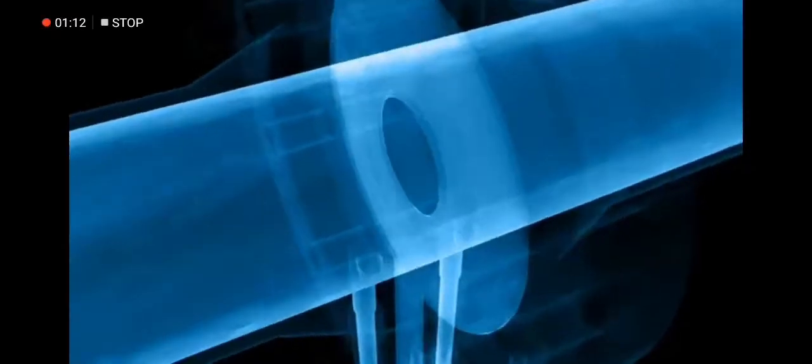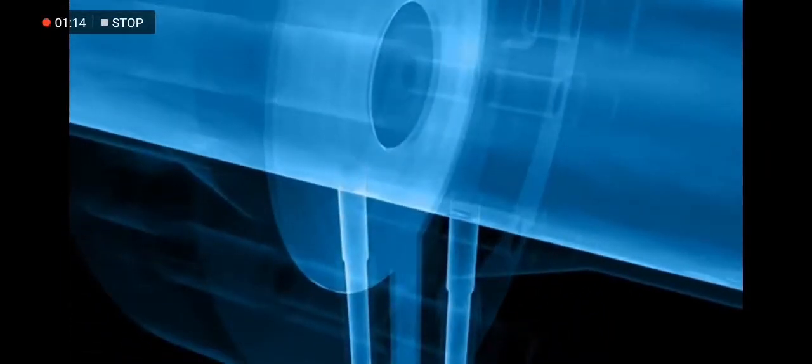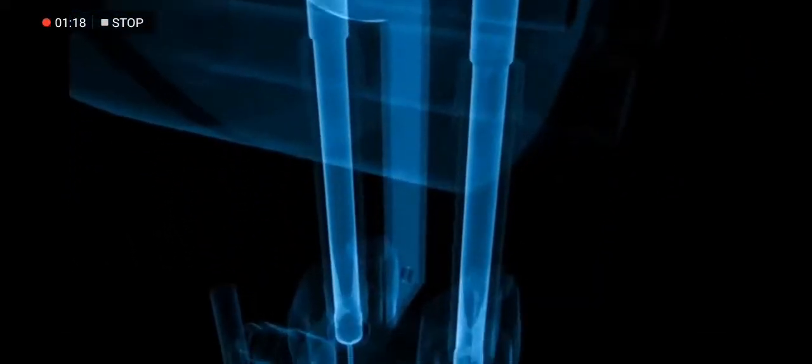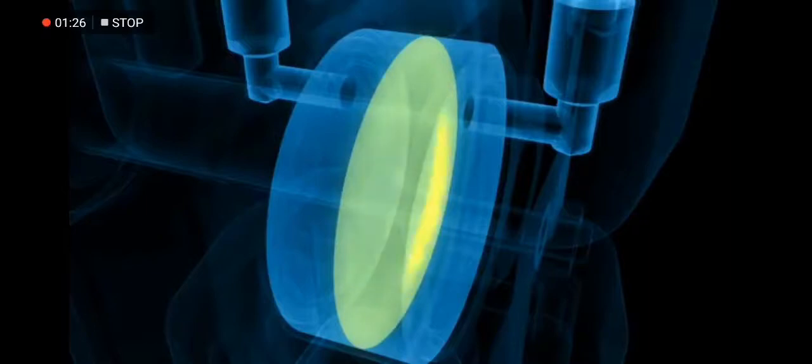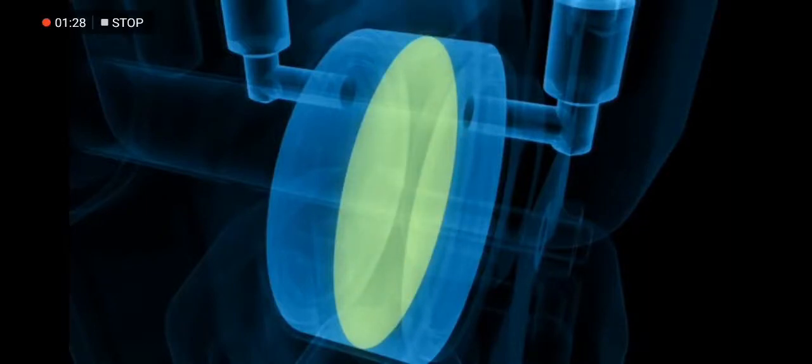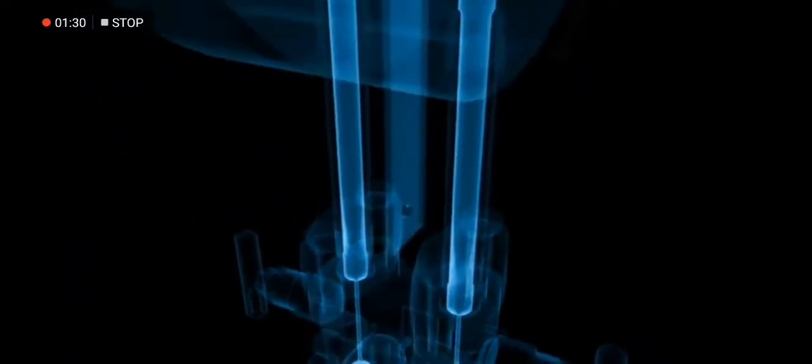Two holes are located in the pipe wall, one before and one after the orifice plate. Two separate tubes connect these holes to a differential pressure sensor, with its two pressure chambers separated by a diaphragm. The tiniest pressure differences in the flowing fluid can be precisely measured.